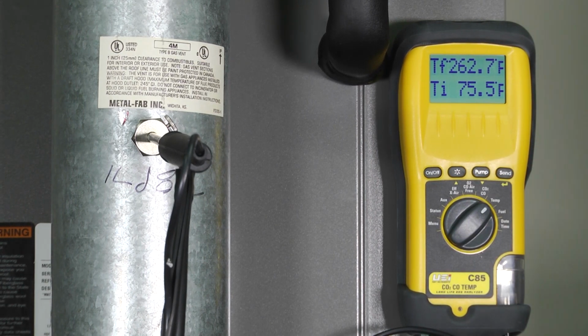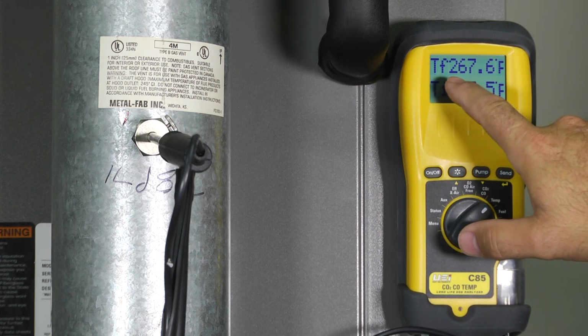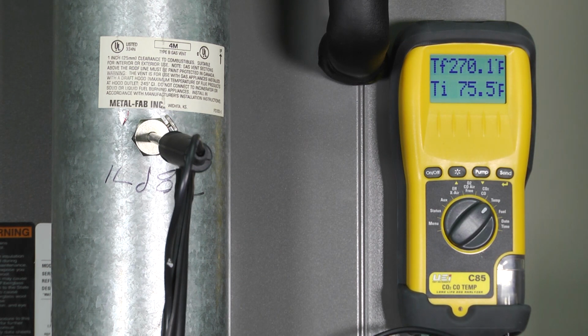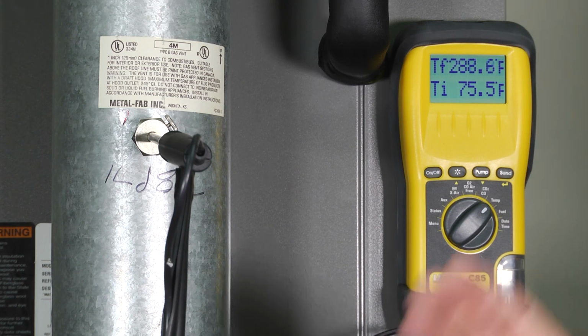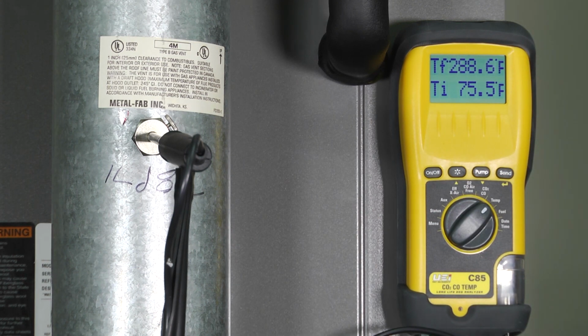And as you can see right here, I'm already looking at what's happening with my temperatures. I can see that I'm reading about 270, 200, and it's climbing. I want to make sure I come to what we call steady state. Steady state just means my temperature is not rising and it's not falling. It's mellowed out and it's at the point where it's going to run all the time. So we're going to sit here and wait. Once our furnace reaches steady state, I'm going to be able to start looking at other things.